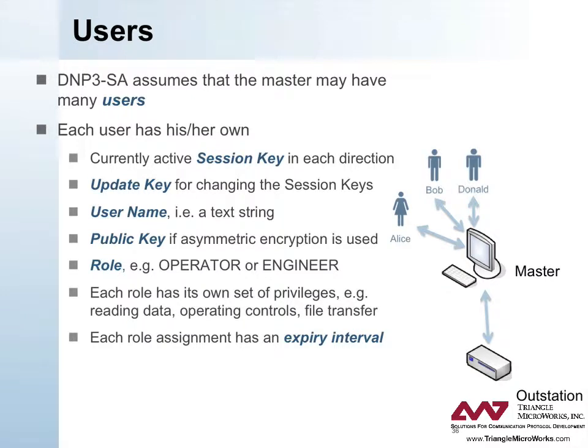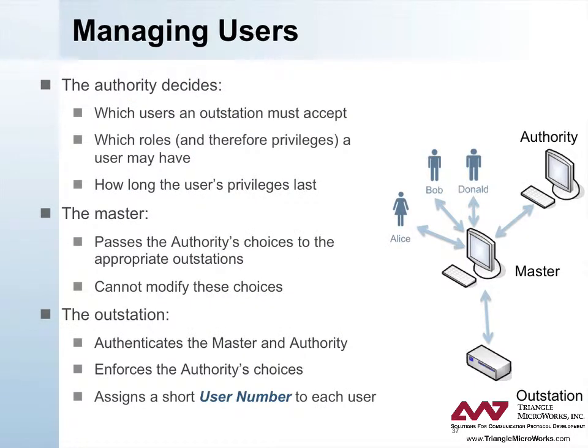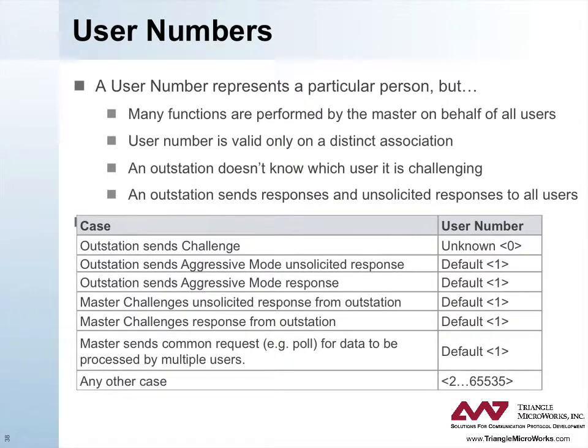DNP3 secure authentication assumes that the master may have many users. Each user has their own currently active session key in each direction. In addition, each user has an update key for changing the session keys, a username which is a text string, a public key if asymmetric encryption is used, and a role — for example, an operator or an engineer. Each role has its own set of privileges, such as reading data, operating controls, or executing file transfers. Each role assignment has an expiry interval as well. The authority decides which users an outstation must accept, which roles and privileges a user may have, and how long the user's privileges last. The master passes the authority's choices to the appropriate outstations and cannot modify these choices. The outstation authenticates the master and the authority, enforces the authority's choices, and assigns a short user number to each user. A user number represents a particular person; however, many functions are performed by the master on behalf of all users. Note that a user number is valid only on one distinct association — that is, the same user can be assigned different user numbers on different links.